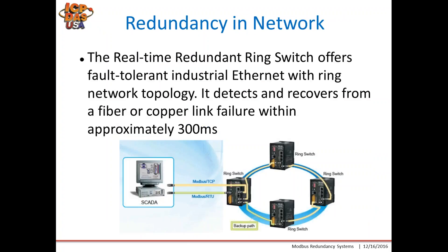Redundancy in networks: the real-time redundant ring switch offers fault tolerance for our ring network topology. It detects and recovers a fiber, copper, or RJ45 link failure within 300 milliseconds. The picture shown here is an example of our ring switches where if any one switch fails, it will have a backup path which it can revert to if communication is lost.